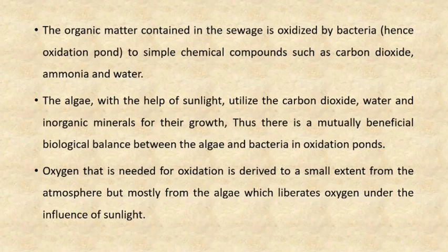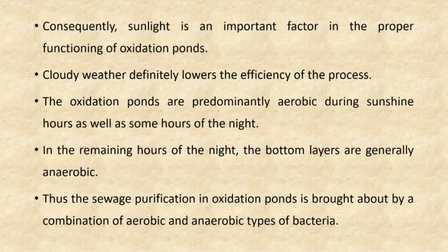The oxygen needed for oxidation is derived to a small extent from the atmosphere, but mostly from the algae, which liberate oxygen under the influence of sunlight. Consequently, sunlight is an important factor in the proper functioning of oxidation ponds.